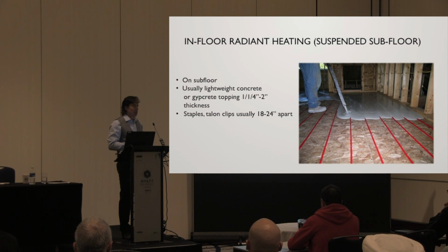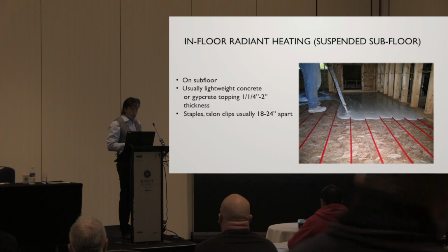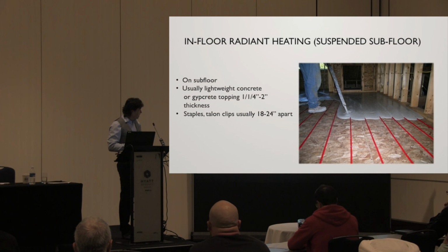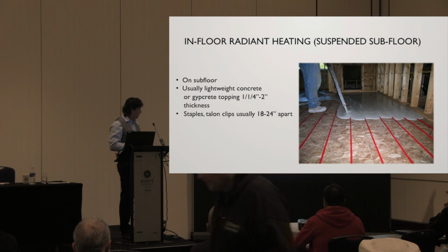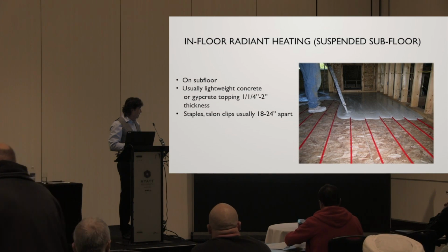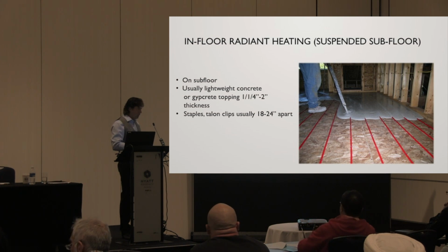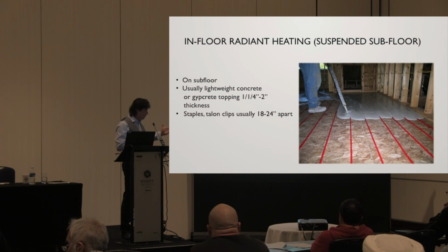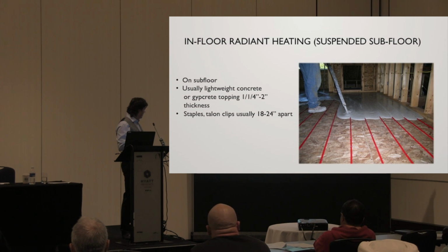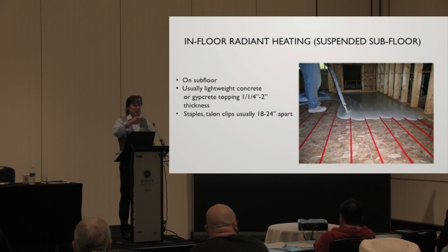It may not leak. So if you're using staples, maybe up the ante, 80 psi or so, as long as your concrete is good with that. Don't get me wrong, staples are fine. They're a good idea. It's just you can get a little sloppy, and so somebody should really walk around and look. That's one way to do it, because you can't really rely on the pressure test. Just make sure you haven't punctured the pipe. Otherwise, Talon clips are safer, just a lot slower. Yes, the gentleman in the back.